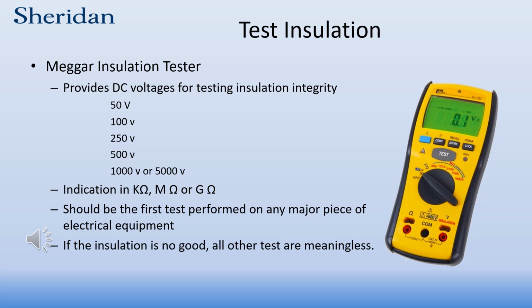This should be performed first on any major piece of electrical equipment. I say major because you wouldn't test every light switch and every light bulb socket that you put in. But if the insulation is bad, all other tests are meaningless. This piece of equipment cannot be used.